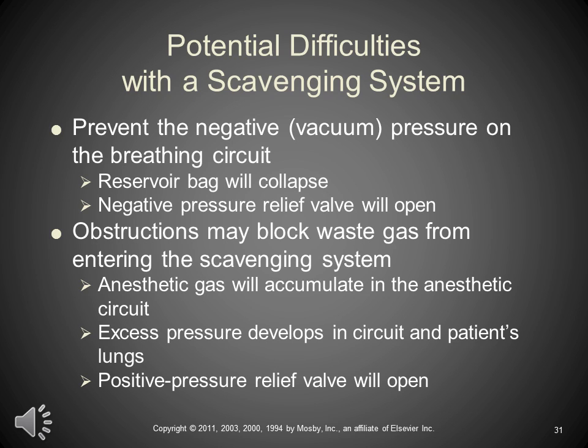Anesthetic gases will accumulate in the circuit. Excessive pressure can develop in that circuit and in the patient's lungs, and at that point the positive pressure relief valve will open. So we don't want to block up the system. Okay, if you block up the system, bad things happen.